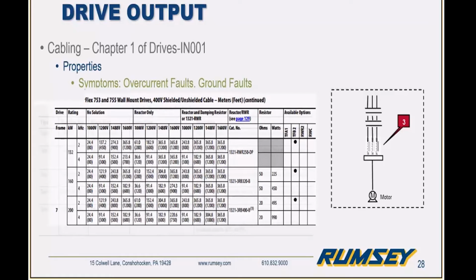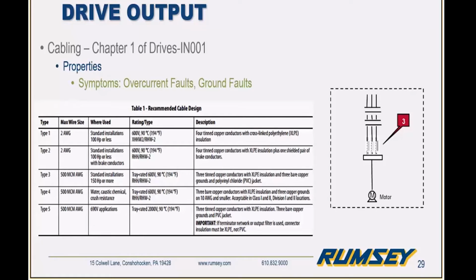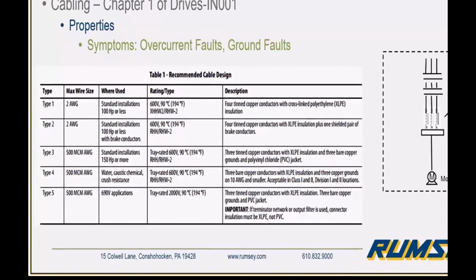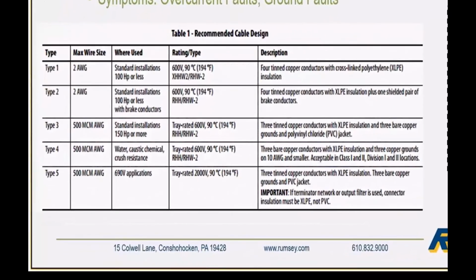Again, moving on to the cable type or types of cables we discussed earlier. In order to avoid overcurrent faults or ground faults from occurring, it's important to look at the actual construction of the cable and the rating of that cable. So based on our installation and what drive size and what we're doing in that particular application, we're going to need to use a specific rating cable. In the drive's guideline manual, there's tables that basically instruct you on what type of cable to use for that installation.